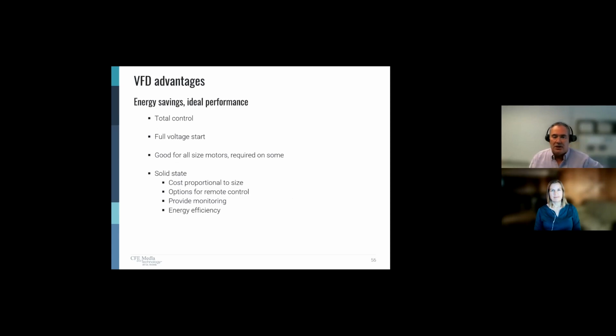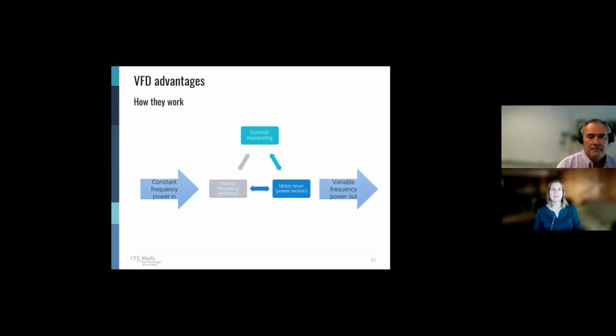They save energy and provide ideal performance. How they work briefly: we put a constant frequency power in, we convert that to DC and then re-invert it back up to the frequency we want. And then we provide that to a driver section and we get variable frequency out. And as we learned earlier, if we adjust the frequency, we adjust the speed of our motor.